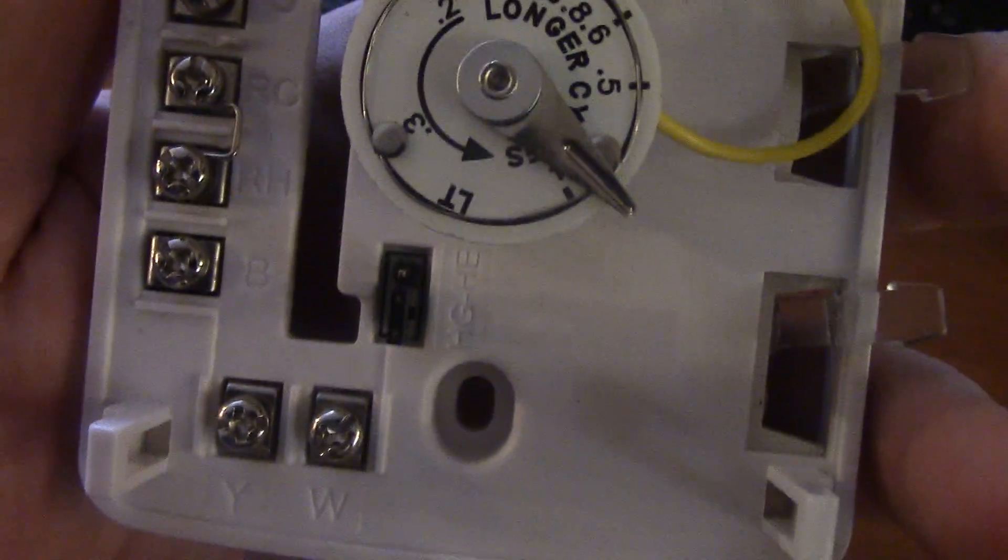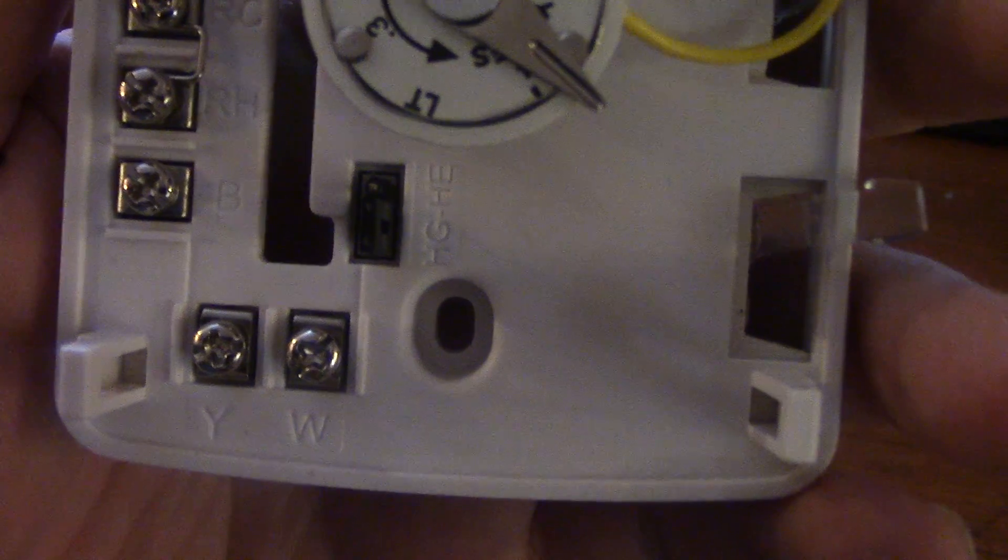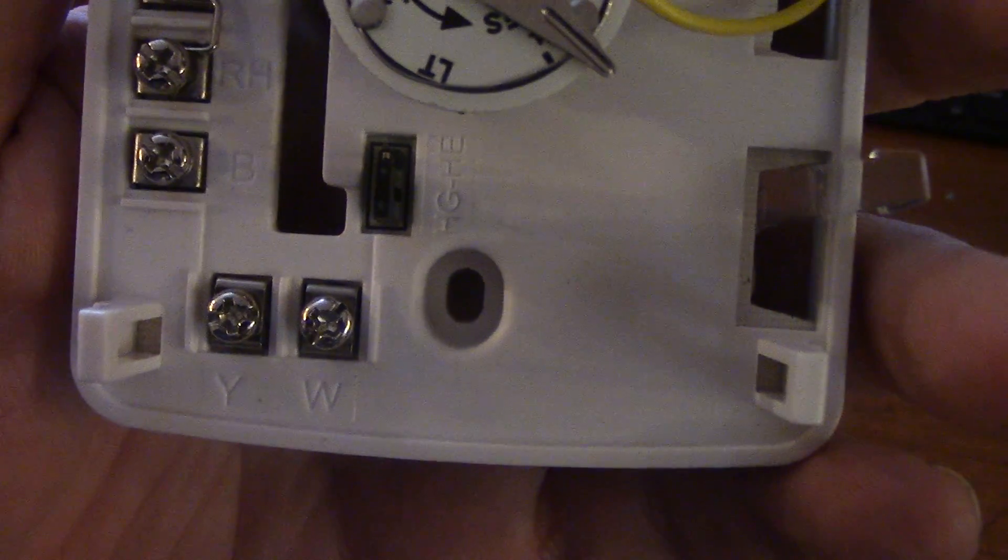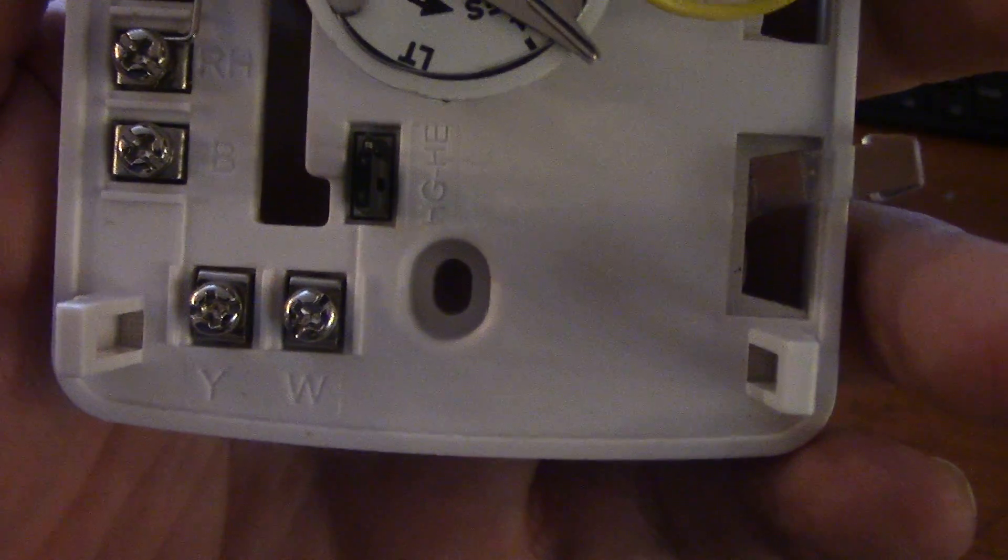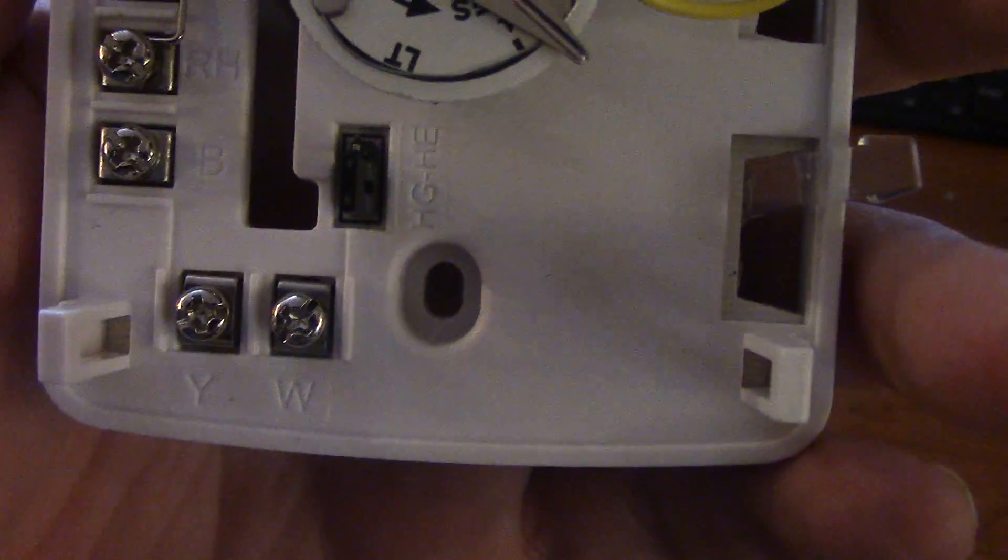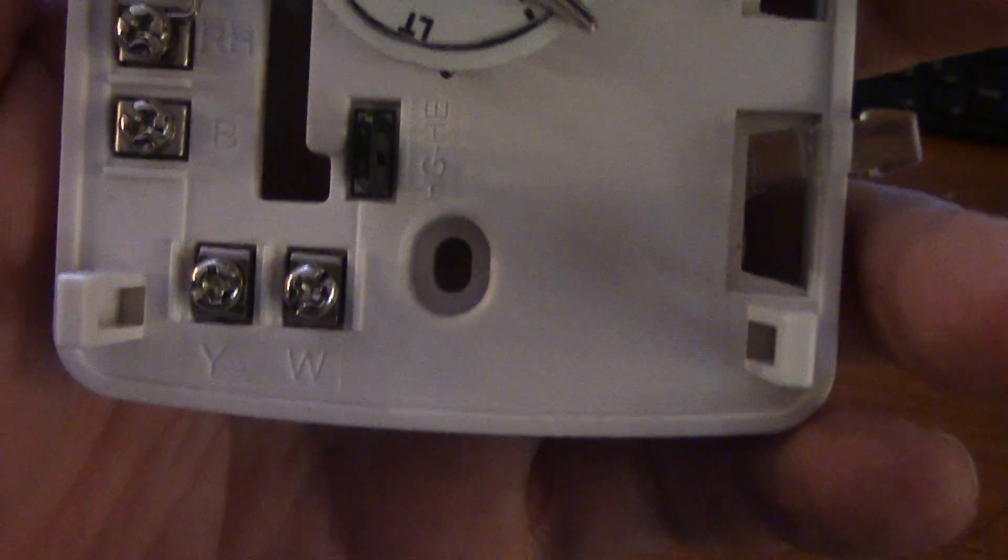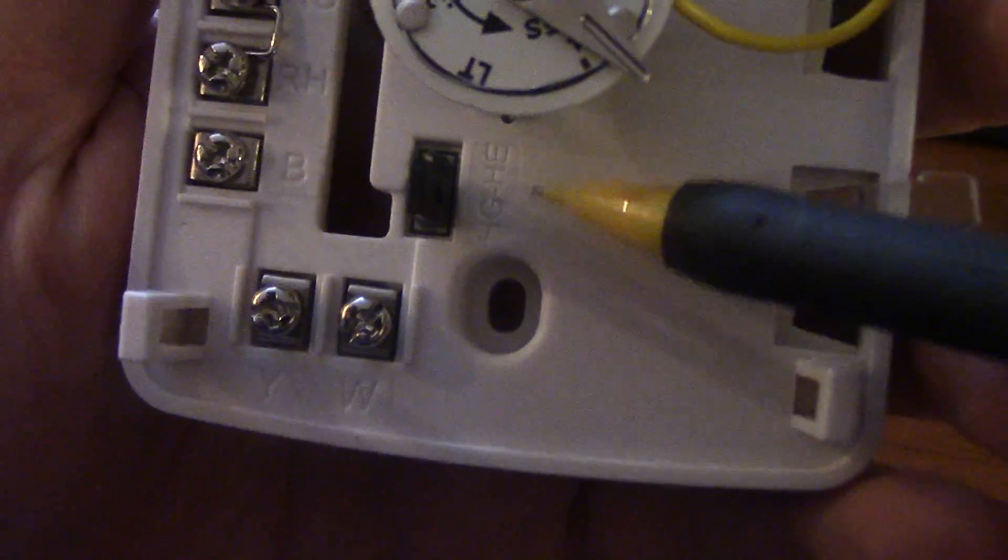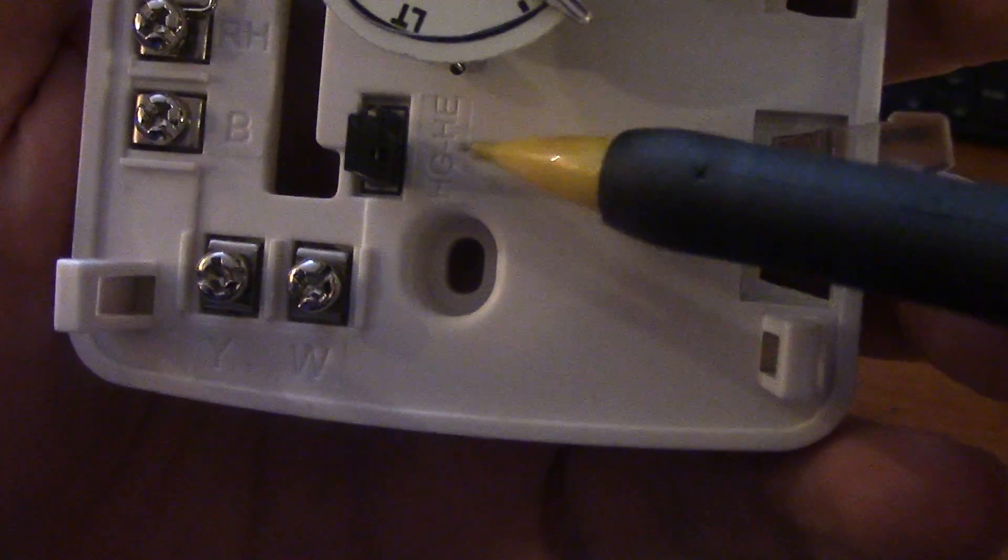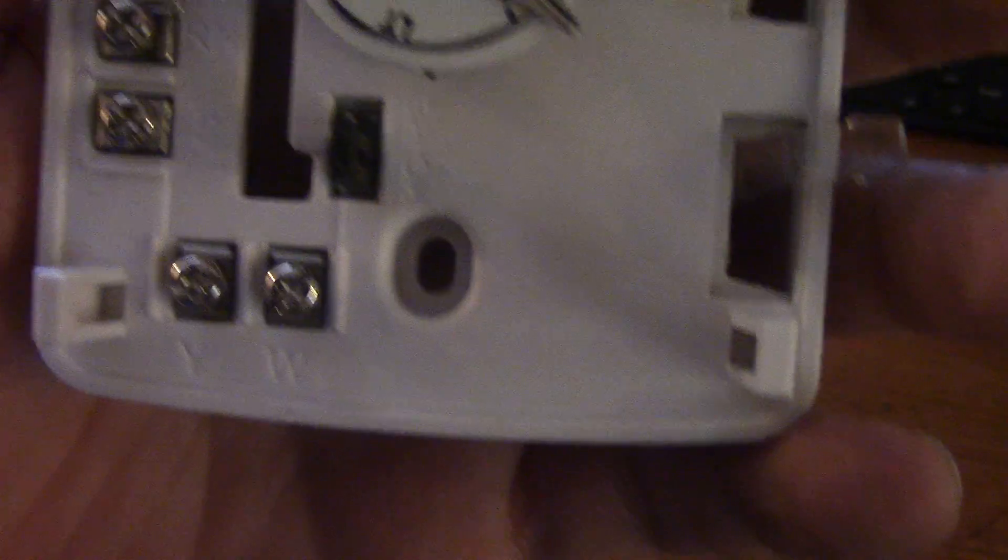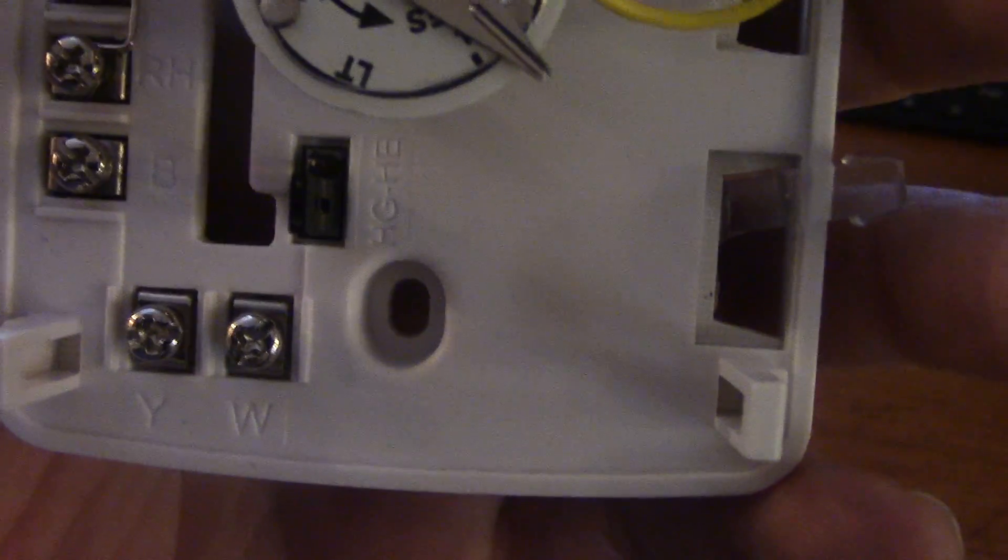What that is is that's your blower control for your furnace. If you have a modern furnace, natural draft furnace, whatever you want to call it and it runs off of gas, you want to put that pin on H G for heat gas. That way the blower, the controls on the furnace, will turn the blower on, not the thermostat.